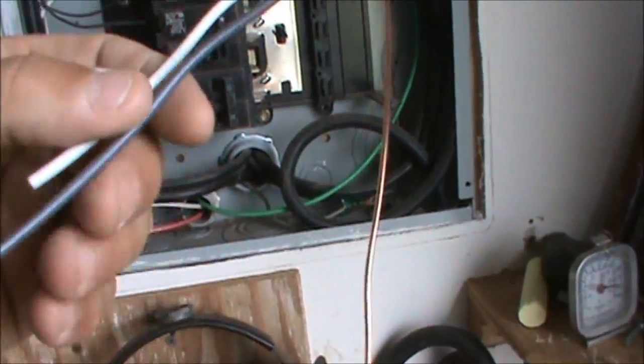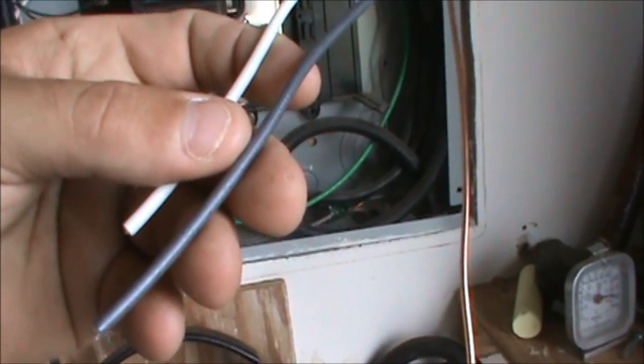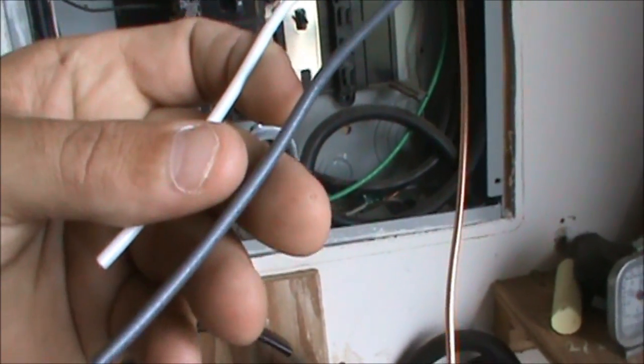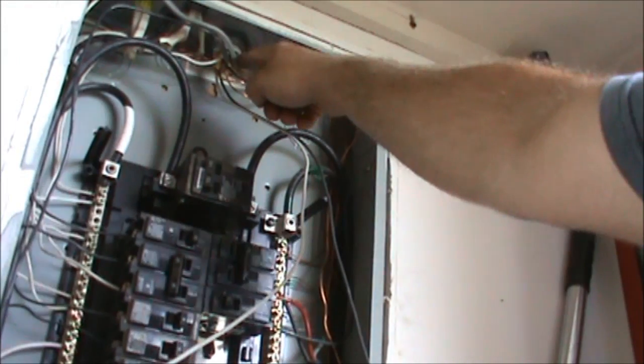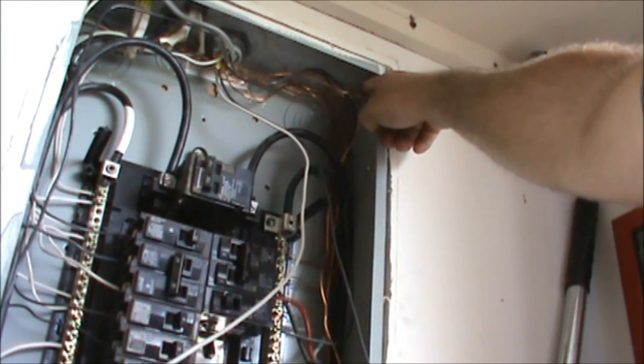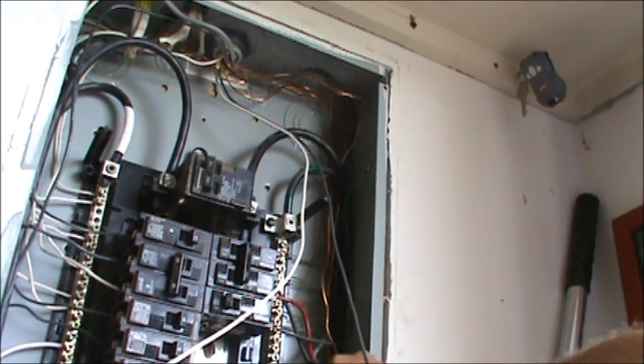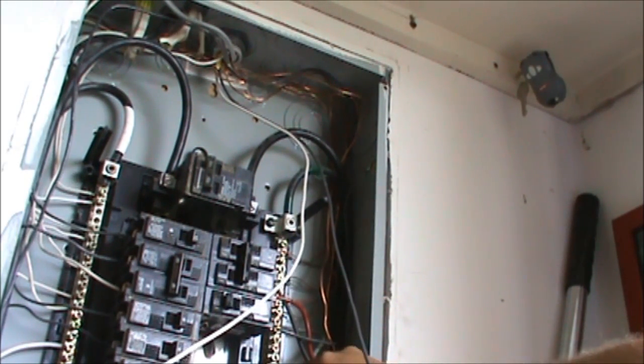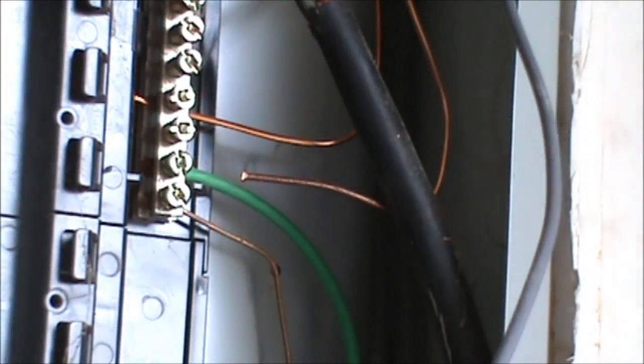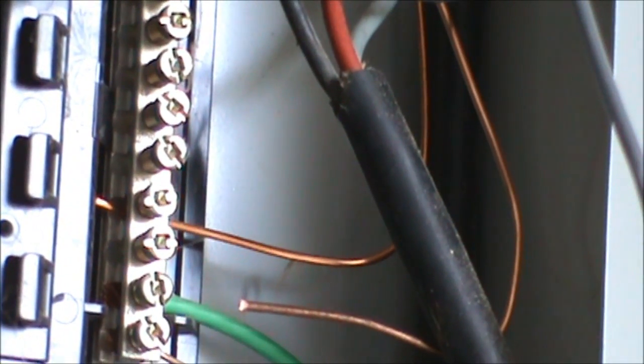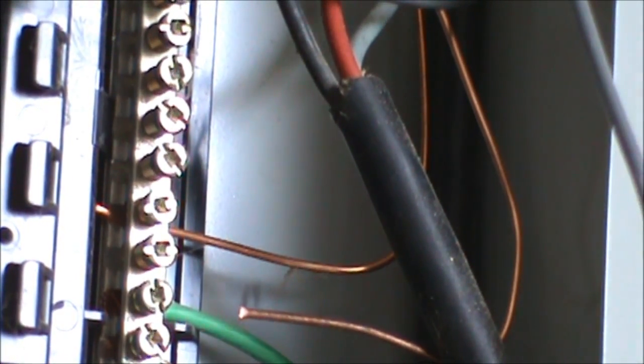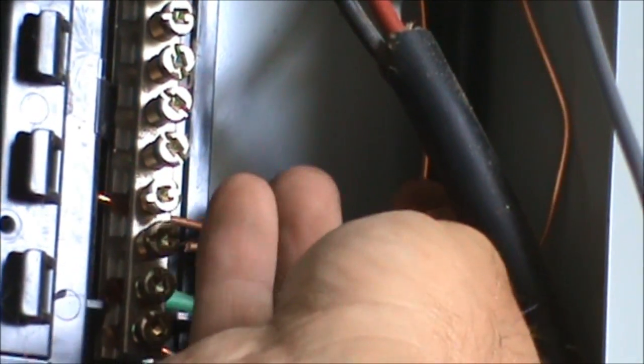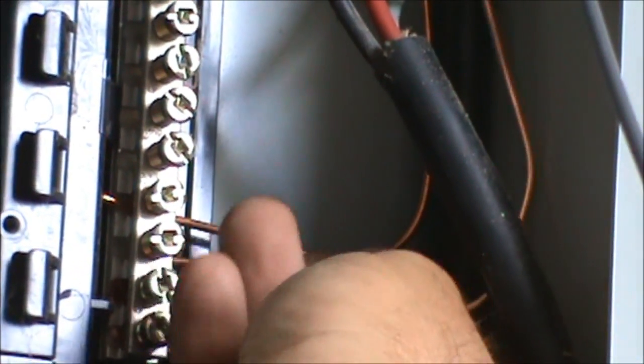Our white and black wires - because we're running a double pole 20 amp circuit, we're going to hook both of these wires, they're both going to be hot, they're both going to get hooked up to our breaker. My ground wire is coming in from the top and it's running up to the top corner like all the other ground wires. I'm just going to show you how to attach that ground wire onto the bar here. So what you want to do is take the wire and carefully feed it in underneath the screw where you want it to mount. You're going to be using just a flathead screwdriver and you want to tighten that up, so you're going to turn this set screw to the right until it seats on that ground.